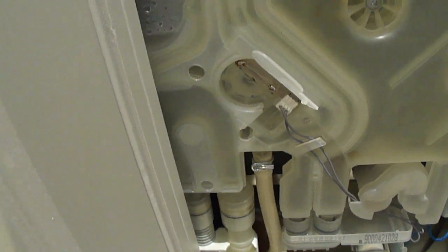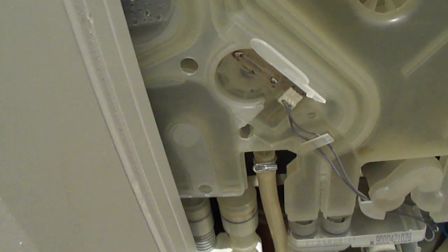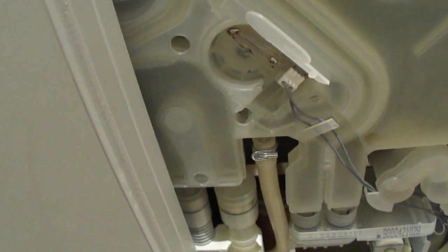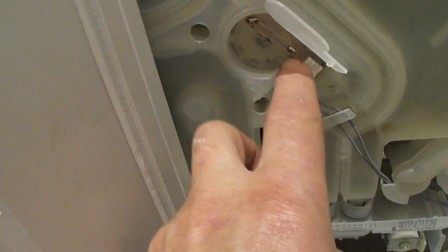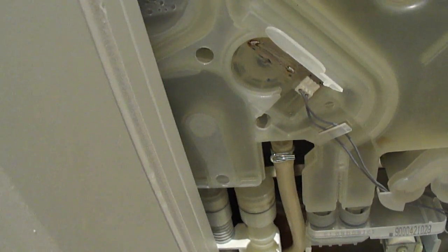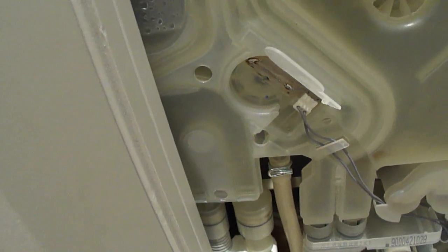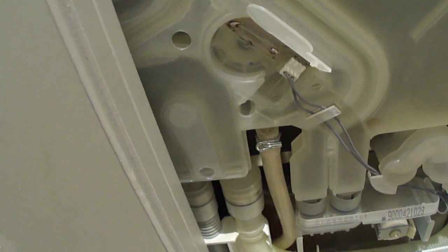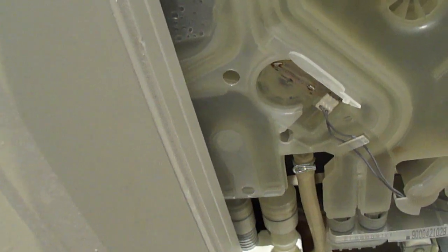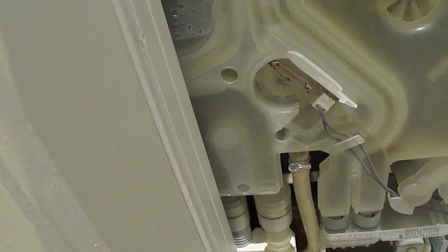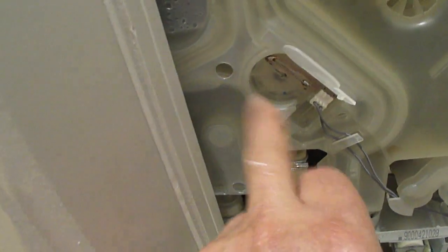So there's various ways you can test that switch. You could do it in situ: turn the power off, take that off, and then start a cycle and measure across the 2 points of the reed switch with a multimeter, put it on continuity - if you've got a buzzer, that's ideal. And what you should hear is when the water is circulating in there, not at the first cycle - it's 3 cycles, I'll probably show you that in a minute - before it actually starts rotating this.